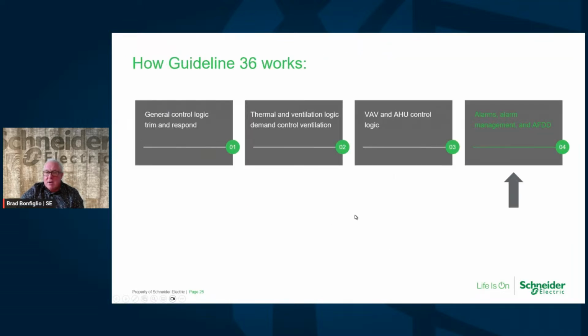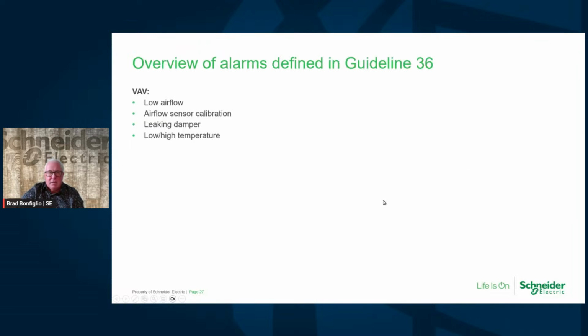Okay, so we went through trim and respond, demand ventilation, zoning of the air handler controllers, and damper control for outside air. Now let's go through alarm management and fault detection. One of the cool things about Guideline 36 is that they actually list out all the alarming that's required. If you're an engineer or a facility manager, instead of always having to ask for these or remember to put them in my spec, these are standard in Guideline 36.